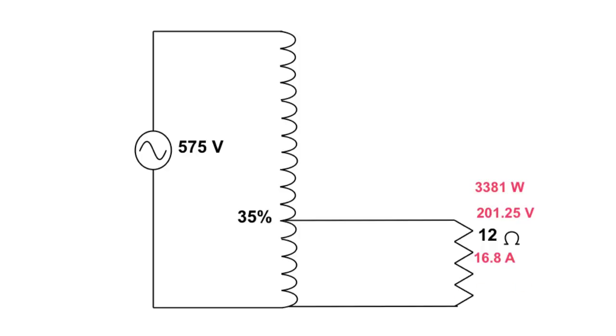Like I just said, whatever this watts is here, it's got to be the same over here, which will give us 3,381 watts on the primary side. Then to get our primary current, all we have to do is take 3,381 and divide it by 575 volts to get a current of 5.88 amps right there.